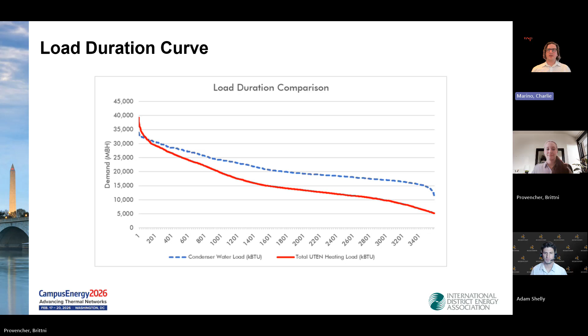When we dig in further, you can see we have a lot of capacity at the central plant, represented in the top left graph. We have a lot of condenser water load, but the actual total UTEN heating load is a bit lower than that, partly because we're not leveraging all of the heat rejection during this pilot project. There are concepts in place for future expansion where we could utilize all the heat being developed from the plant, but for now we're not meeting all of those hours.